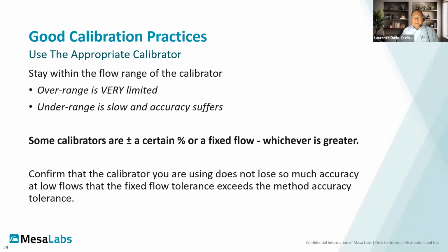Good practices. This is part of avoiding blame. Use the appropriate calibrator. Again, I tend to go with primary calibrators. I haven't used a secondary calibrator in I can't remember when, because it gives me a level of protection in terms of legal defensibility. Stay within the flow range of the calibrator. It's not too much of a problem with over ranges. Most of the electronic calibrators will simply shut down and quit reading if you go to an over range. If you go to an under range situation, it's slow.